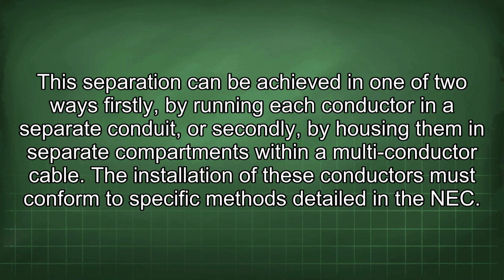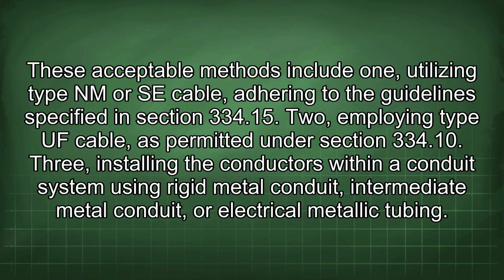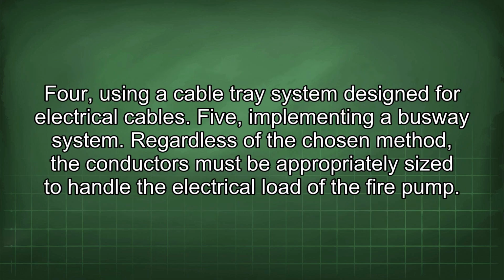Firstly, by running each conductor in a separate conduit, or secondly, by housing them in separate compartments within a multi-conductor cable. The installation of these conductors must conform to specific methods detailed in the NEC. These acceptable methods include: 1. Utilizing type NM or SE cable, adhering to the guidelines specified in section 334.15. 2. Employing type UF cable, as permitted under section 334.10. 3. Installing the conductors within a conduit system using rigid metal conduit, intermediate metal conduit, or electrical metallic tubing. 4. Using a cable tray system designed for electrical cables. 5. Implementing a busway system.